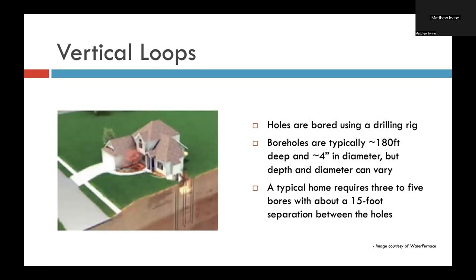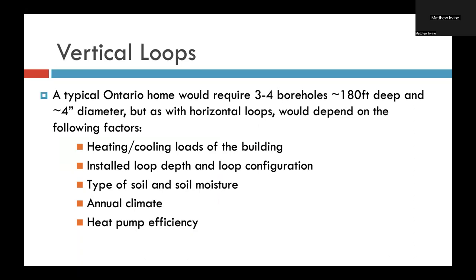Vertical loops are holes that are bored using a vertical drilling rig. These boreholes are typically about 180 feet deep and about 4 inches in diameter. Depth and diameter can vary though. And a typical home would require 3 to 5 of these boreholes at about a 15 foot separation between them. Next, please. So a typical Ontario home would require 3 to 4 of these boreholes, again about 180 feet deep and 4 inches in diameter, but as with horizontal loops, it would depend on the same factors: the heat loss and heat gain calculations, the loop depth and configuration, the type of soil and moisture, the annual climate, and heat pump efficiency.